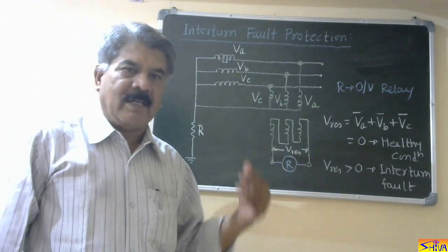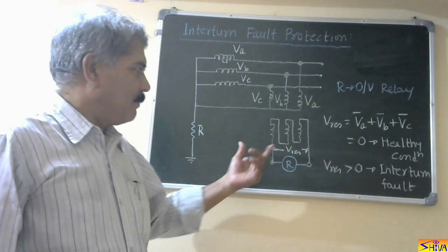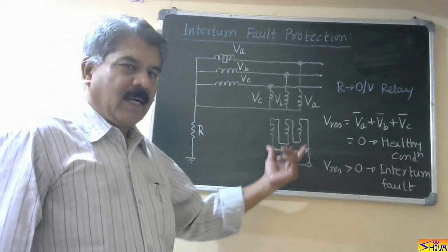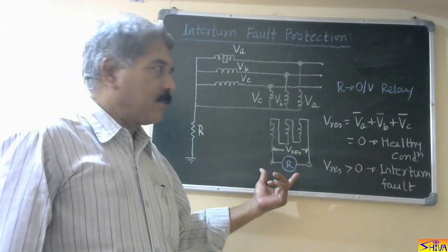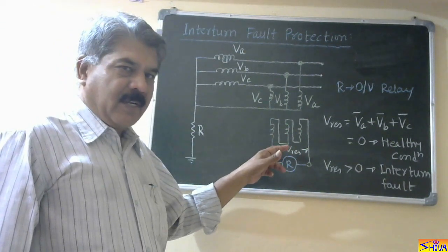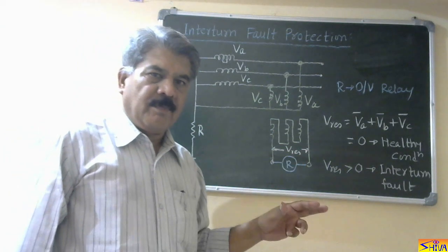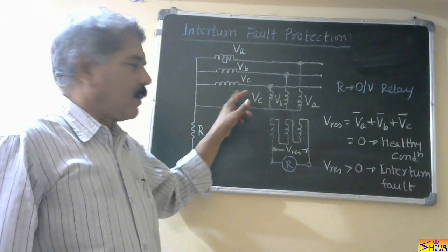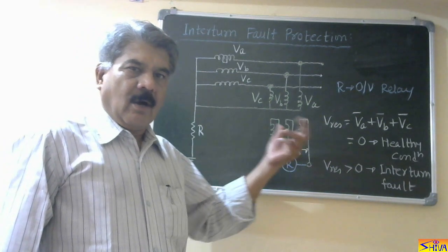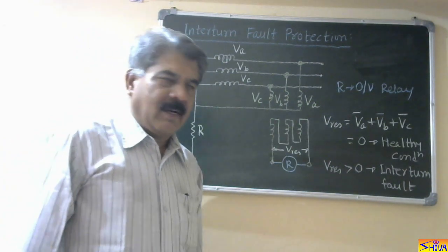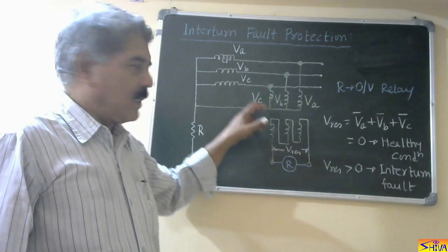We have to use a separate scheme. First, I will discuss the scheme with open delta secondary of a potential transformer. This type of protection against inter-turn faults is used depending on the number of layers in the winding. It can be single-layer or double-layer winding. In the present case, I have shown a single-layer winding for the generator.